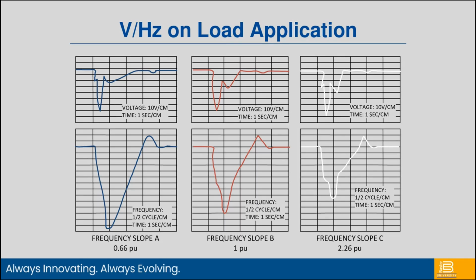So that's why we add a volts per hertz limiter or a frequency limiter into the scenario. So now I have that initial load, my voltage drops, my frequency drops. Based upon that amount of frequency drop, I'm going to back off on my excitation and allow some time for my prime mover to recover. And we can tune this based upon our load. So we can tune our volts per hertz curve. We have different sets of volts per hertz curves that can be used to get the response that we want out of the machine.